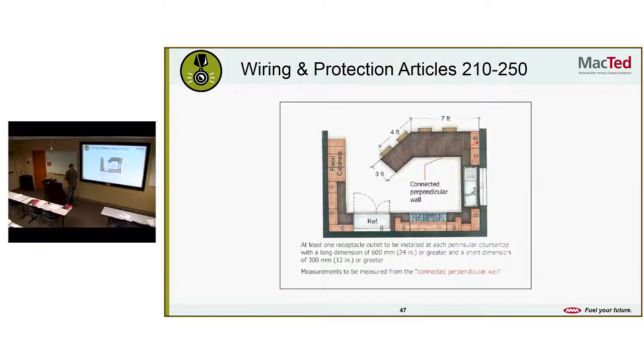Into the peninsula, yeah. So now there's clarification: you need at least one receptacle outlet installed at each peninsula countertop with a long dimension of 24 inches or greater. So if you're going to do a peninsula, make sure you have an outlet down here at the perpendicular wall, as they call it. And you should probably have one at the end on the face down here would probably be a good idea.